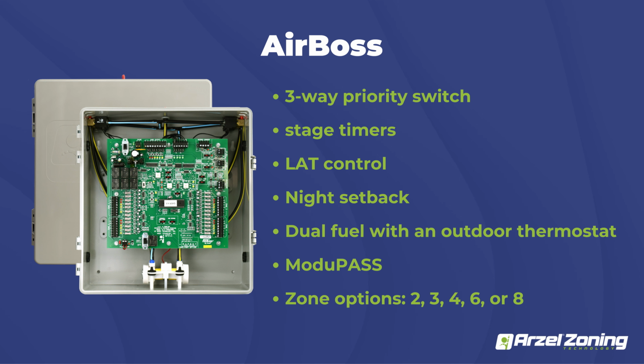One of the things that it does incorporate is a master zone switch. Basically you can either flip the switch for the master zone, or you can put a timer or a thermostat with dry contacts that close the terminals at a certain time. So there are a lot of different ways you can do it, but if that master zone switch is activated, it reverts all functionality to the zone 1 thermostat.